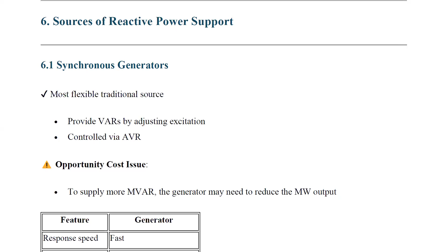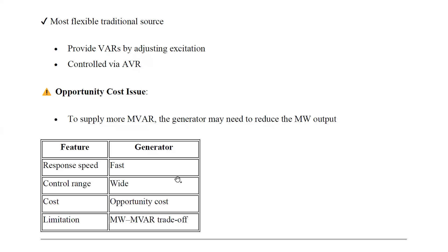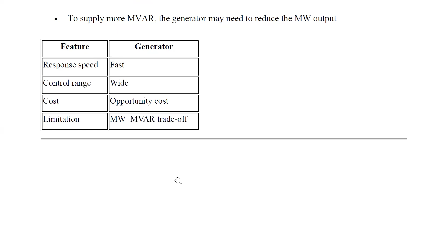Response speed: generators are fast, and the control range is wide. Cost: there is an opportunity cost, because to supply more reactive power the generator may reduce its megawatt power output. That you also need to take into account. Next, the limitation. What is the main limitation? Megawatt-MVAR trade-offs, which are there in the generators, or in a restructured power system, controlled within the generation companies.